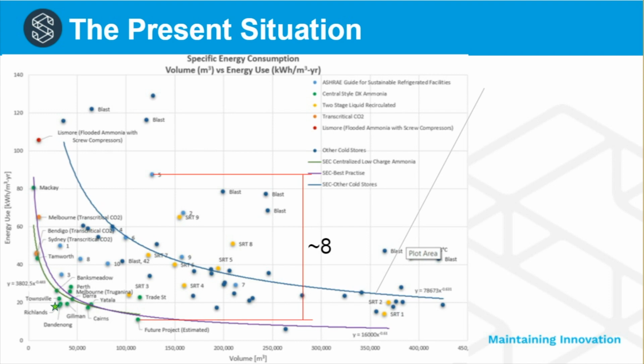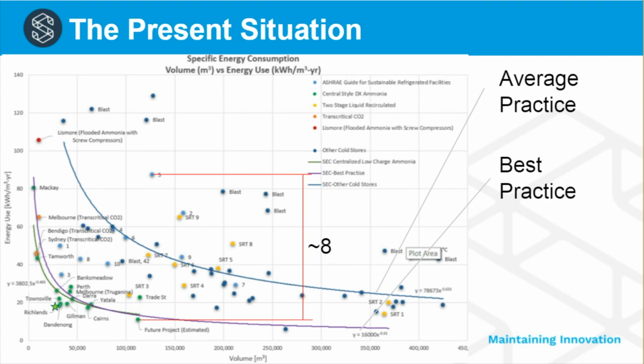And what I've attempted to do here is draw two graphs. The graph in the middle, this is the blue one, is what I call average practice. You can see it there. And the next graph down is what I have called best practice here. Now, the best practice graph is simply a polynomial regression analysis through some recorded SEC values for centralized low-charge ammonia systems. The average practice is a polynomial regression analysis through some other SEC values for conventional liquid overfeed systems, okay?